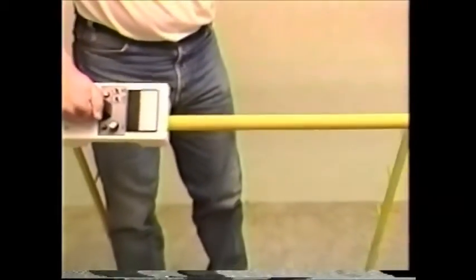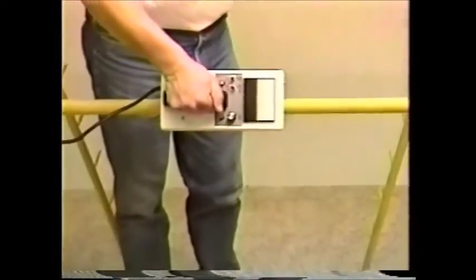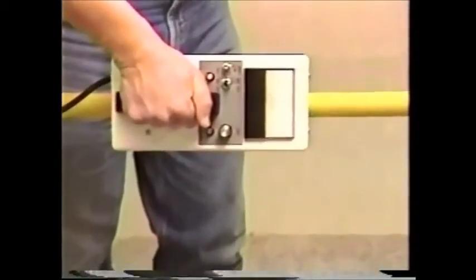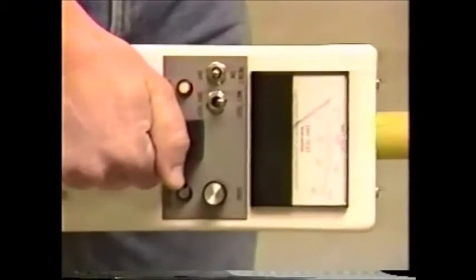As we retest the tool, we observe an obvious change in the reading. While the tool went off scale before cleaning, we are now reading 30 microamps.